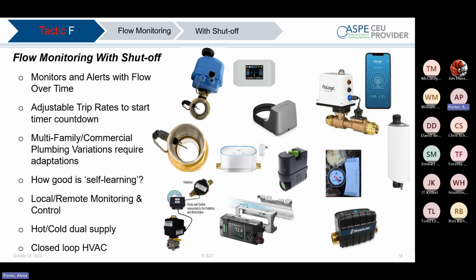Tactic F would be flow monitoring with automatic shutoff, certainly more than 14% effectiveness in preventing catastrophic damage. Some of these options are algorithmic or have a learning cycle of water habits, and certainly others are suitable for both hot and cold supply, some not, with more plastic connections. With commercial applications, if you can zone the building out with these more enhanced mitigation options, it offers more protection to avoid catastrophic water damage.